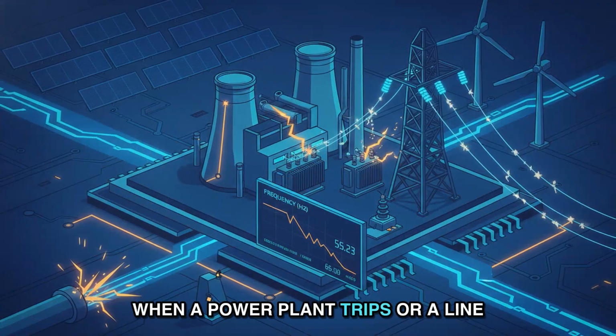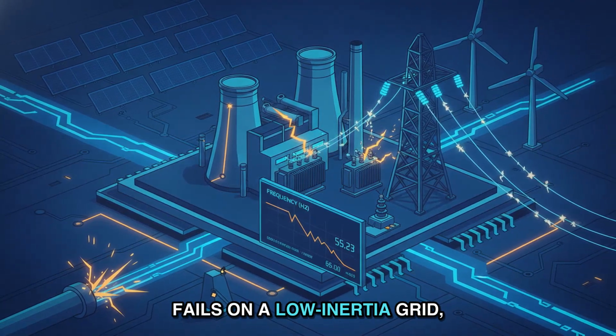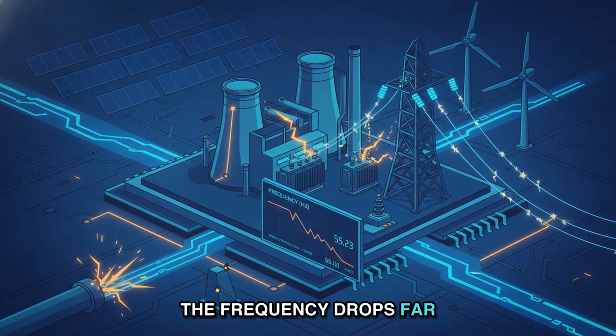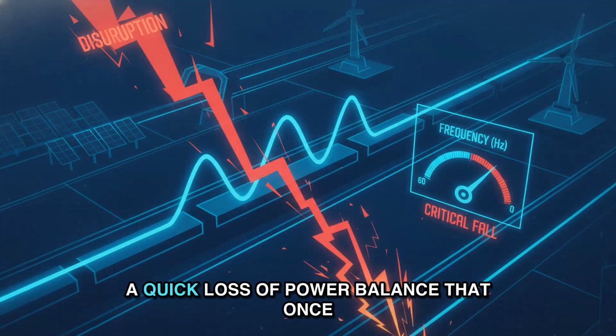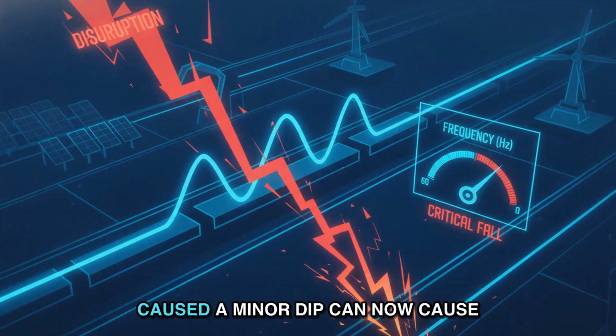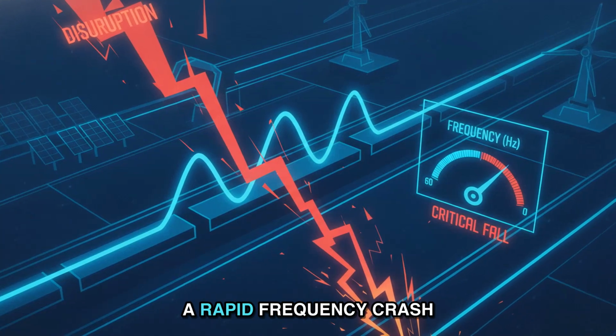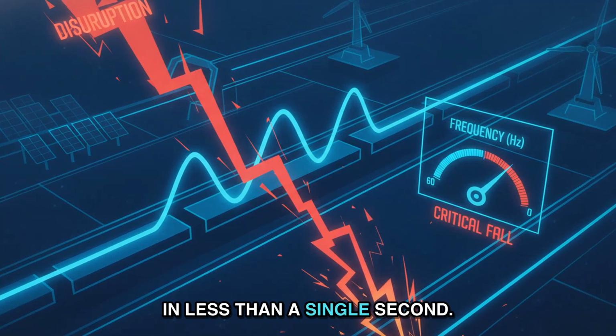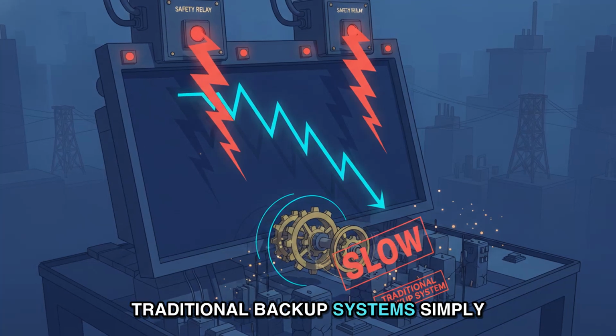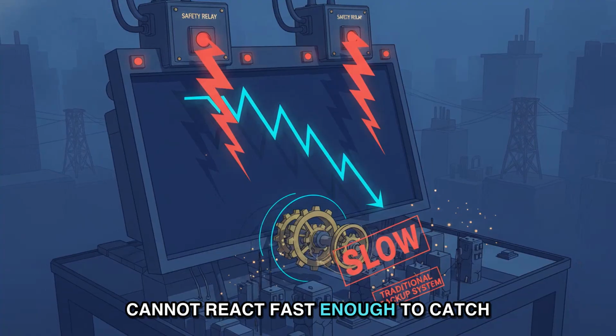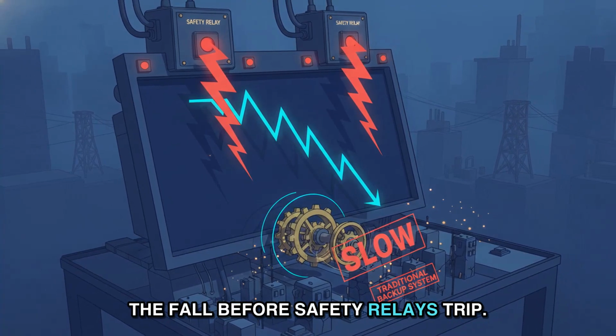When a power plant trips or a line fails on a low inertia grid, the frequency drops far faster than it used to. A quick loss of power balance that once caused a minor dip can now cause a rapid frequency crash in less than a single second. Traditional backup systems simply cannot react fast enough to catch the fall before safety relays trip.